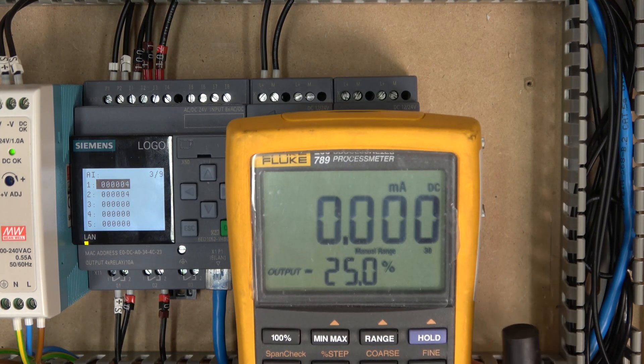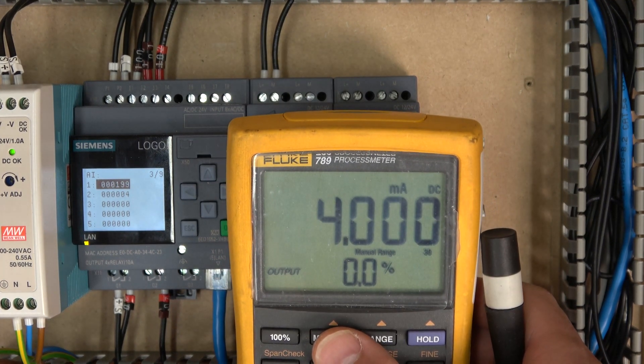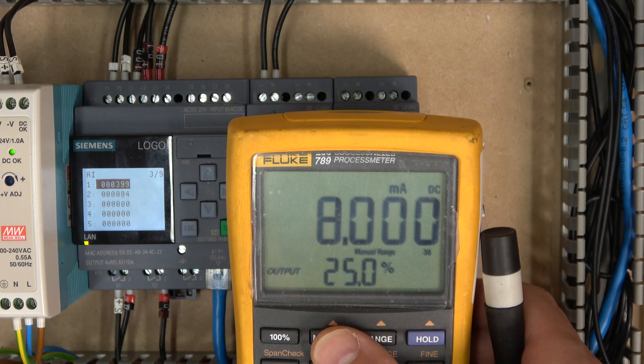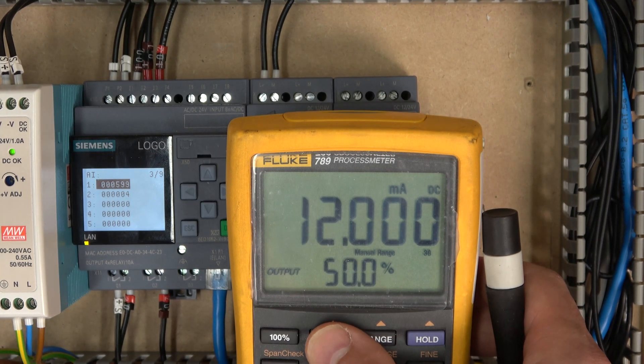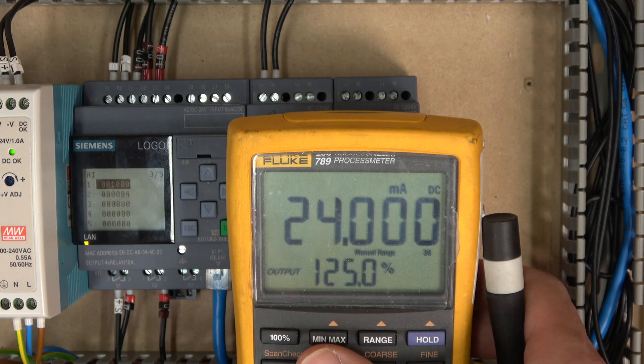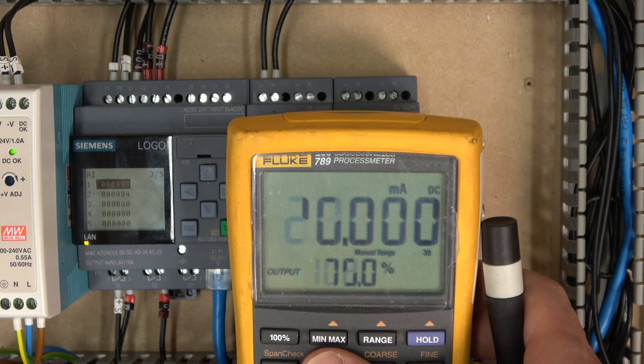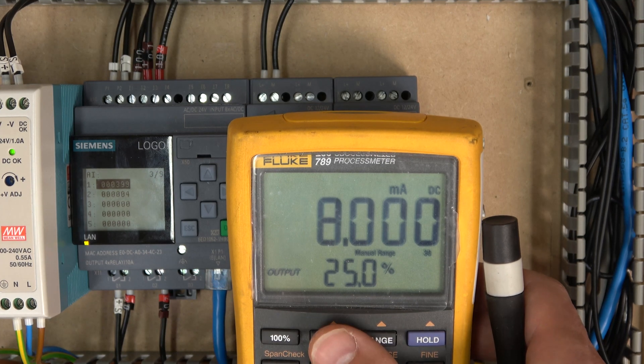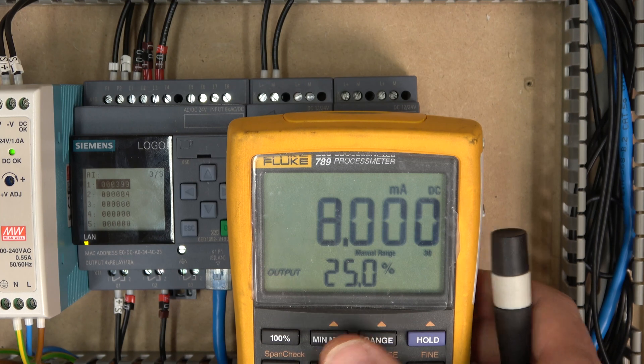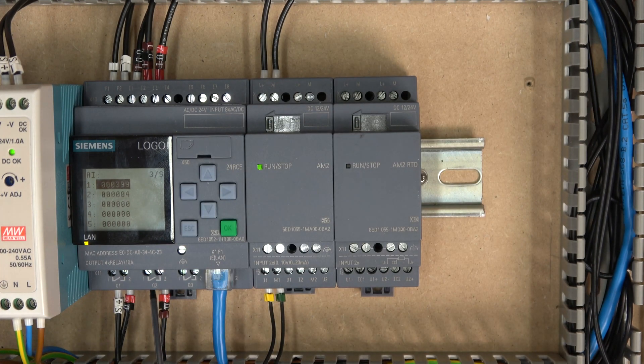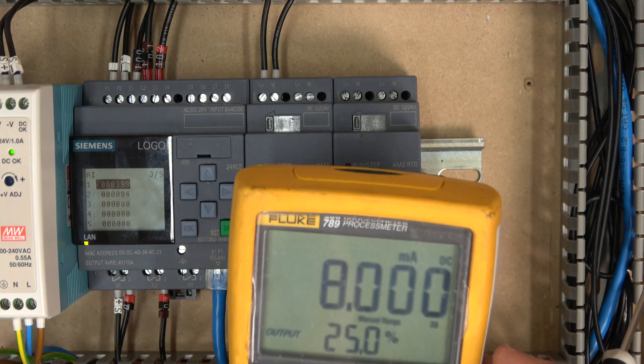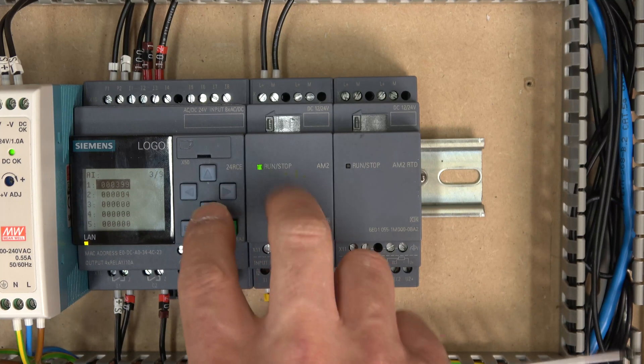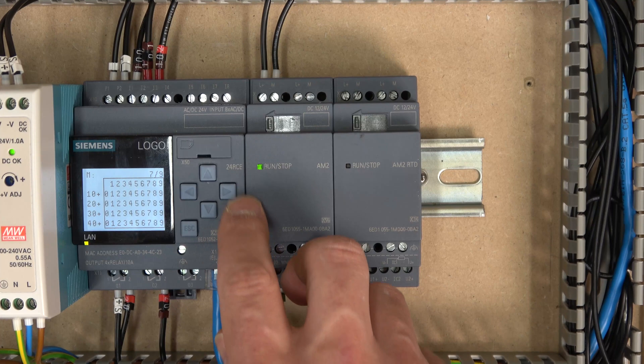So as you can see down here, as I move my milliamps up, the values will be changing, and it comes from zero all the way to 1,000. So in the software, we've created a small program where we're comparing. Turn things on when you reach 600 and turn things off at 450. I have not put a live cable to my relay. So at the moment it's relay switching, but nothing is coming on.